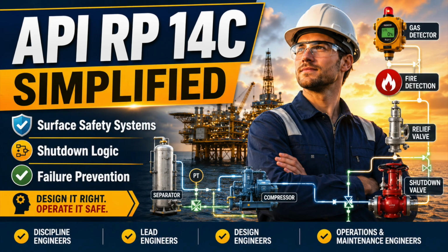A disciplined analysis begins by defining each process component and its actual safety boundary. That boundary is not limited to the vessel shell, compressor casing, or pump body. It includes the connected inlet piping, outlet piping, valves, chokes, branches, and restrictions until another protected component takes over responsibility. This is where hidden gaps often appear. The vessel is protected, but the lower rated pipe between the vessel and the next isolation point is not. The compressor discharge is protected, but the cooler between the machine and relief connection has a lower design pressure.